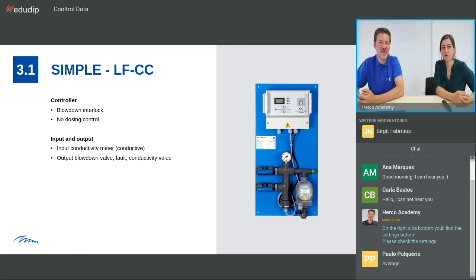We have very few inputs and outputs here. One input is, of course, the conductivity meter, obviously. And it's worth mentioning also that in this blowdown controller, there's only a conductive measurement available. In our other ranges, we have conductive and inductive measurements. There's as output, of course, the signal for the blowdown valve to open or shut. There's a fault that is shown here, I think, with an LED. Yes. And the conductivity value can also be sent as an output of 20 milliamperes to, let's say, a central control system.